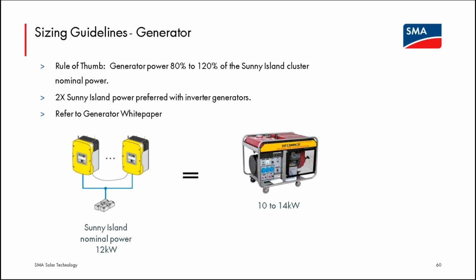If there's a generator in the system, generally a quote unquote dumb generator, somewhere right around the same nameplate of the generator as the sum of Sunny Island powers is what we would like to see. If it's a newer inverter style generator, we would actually ask for twice the nameplate on that generator than the sum of the Sunny Island powers. That will allow that inverter generator to operate far more beneficially. We've seen problems with smaller inverter generators. So again, those 2 rules of thumb are based on the operating style of the generator, and the generator white paper that I call out in this last bullet point is a technical document on the Sunny Island US product page that talks about what styles of operation of generators are compatible and sizing requirements or guidelines.